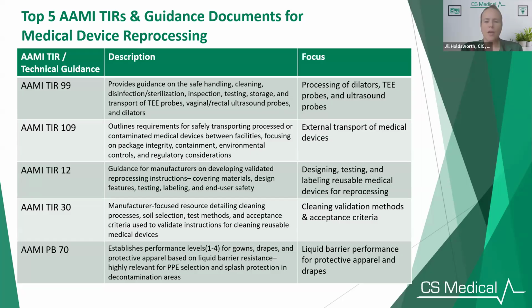But I'm going to go down to PB70. This one is very important because this is your protective barriers. And the reason I bring this one up is because this is going to speak directly to what your reprocessing staff must wear at minimum to make sure that they're protected. We see a lot of strike-through, which is that kind of wetness that goes through the gown at the level of the torso where they're leaning against the sink. So if you have strike-through on your gowns, then we want to make sure that they're wearing a gown that's protective, that's not potentially exposing them when they're leaning against the sink. I have recommended to people that strike-through should be a safety event going into your safety system.